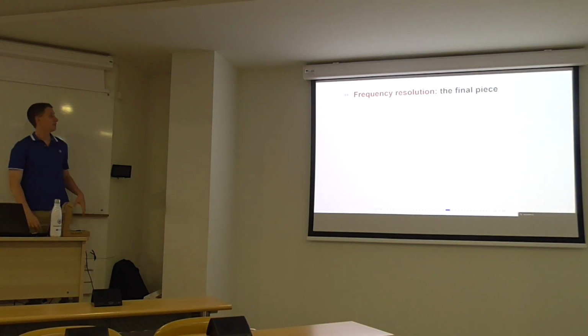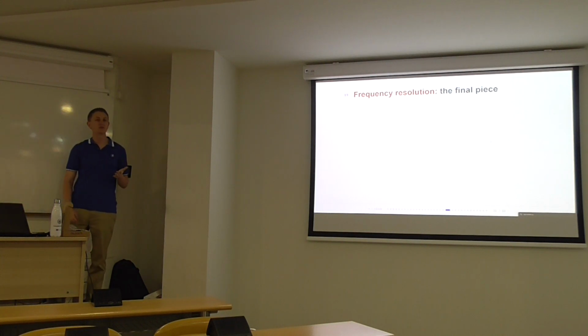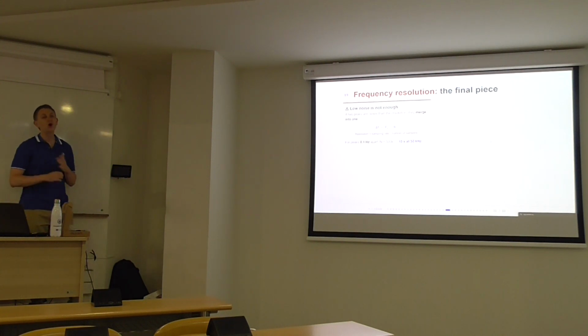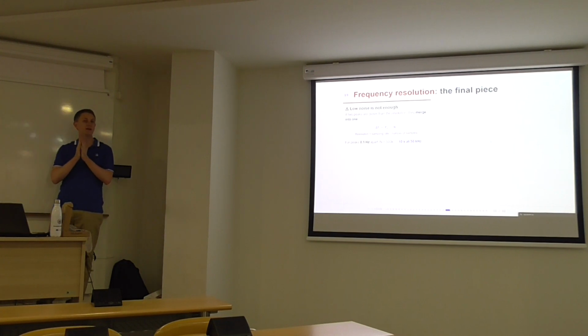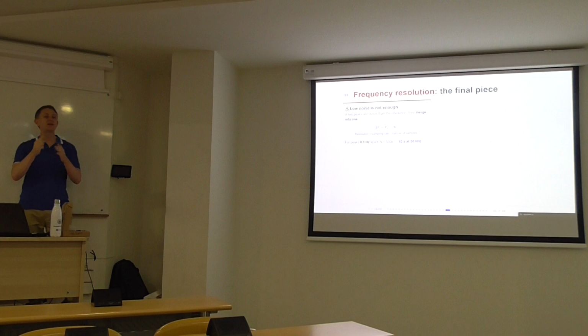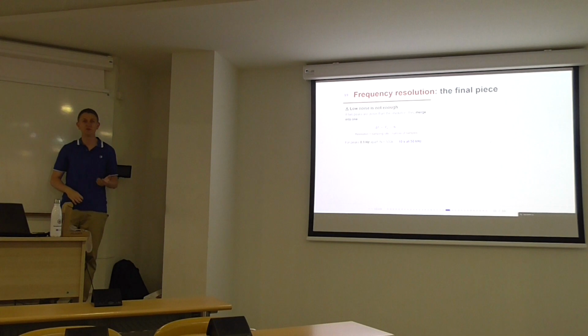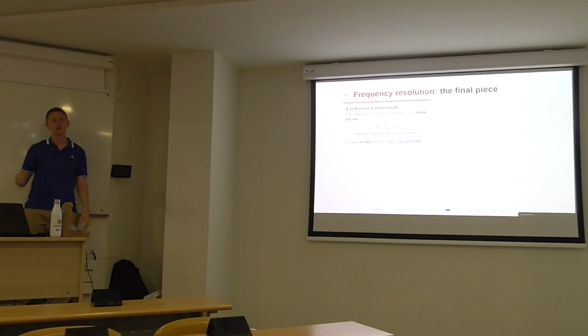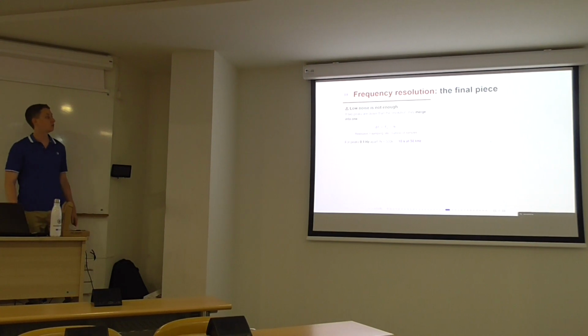Well, and finally, what I call the final topic is the frequency resolution. Low noise is not enough. If two peaks are closer together than the resolution, they merge into one single peak. So you cannot know if it is the broken rotor bar harmonic, the fundamental component, or another harmonic that has merged into one. What is the frequency resolution? It's the inverse of the capturing time. So if I'm capturing 50 seconds, 1/50 Hz is your frequency resolution.